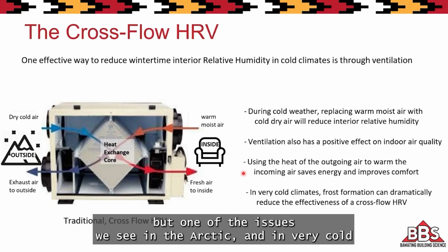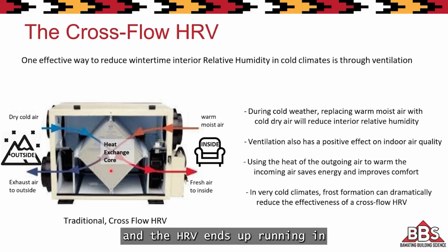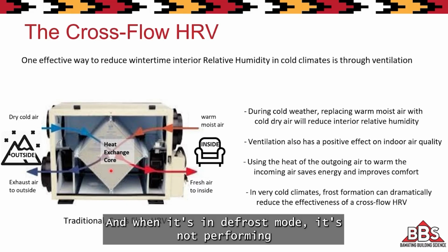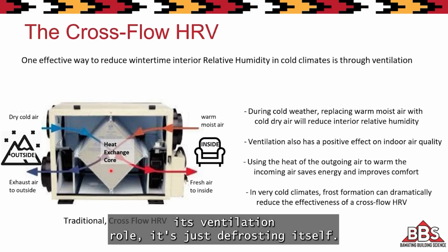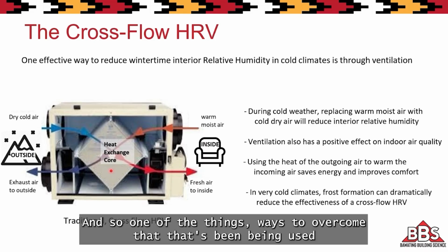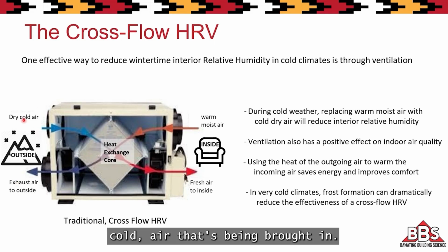But one of the issues we see in the Arctic and in very cold climates is that frost formation inside of this core is a real problem. And the HRV ends up running in defrost mode for a significant amount of time. And when it's in defrost mode, it's not performing its ventilation role. It's just defrosting itself. And so one of the ways to overcome that, currently being used in the Arctic, is to preheat that cold air that's being brought in.